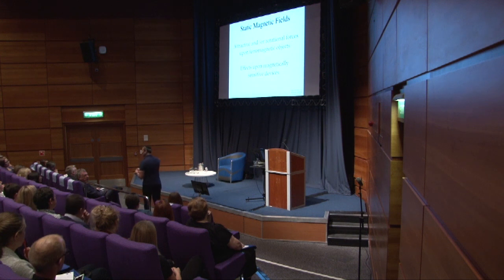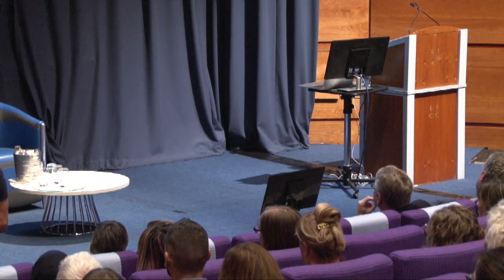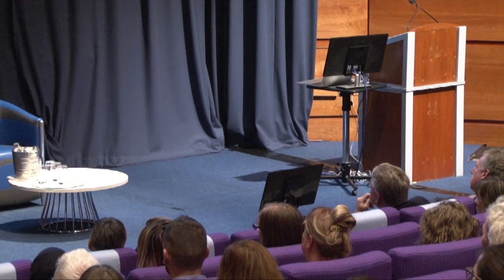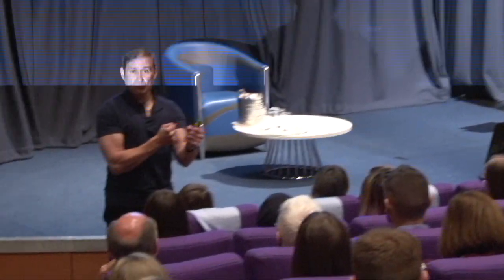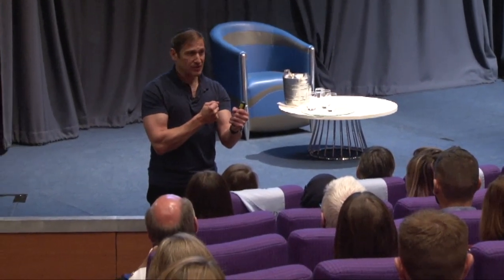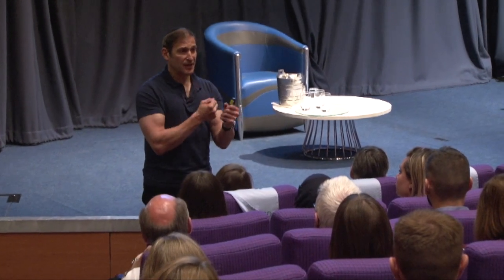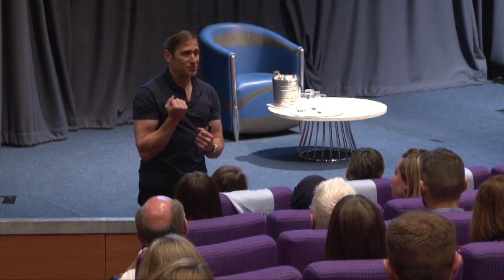We're testing them, and in one position it's fantastic—exactly what it's supposed to do. I measure it and it says 6 liters O2, and indeed 6 liters per minute are being delivered. Then you reposition the oxygen tank perpendicularly, and the oxygen flow goes to zero.